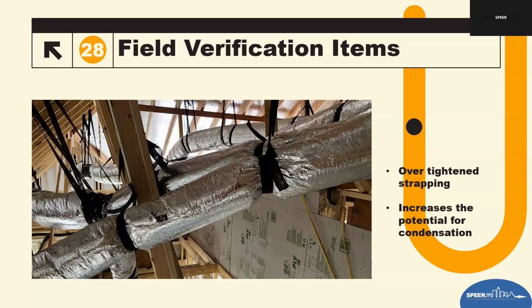So we need to make sure those are not over tightened, because that will build up more heat in the duct. The system will produce 55-degree temperature, and at the supply vent you're only getting 67. That's going to be contributed by this. Things like this, sharp bends, kinks, laying against framing members, touching roofing decks, overstrapping of the insulation, all increase temperature running down the duct. So now we're not worried about how much CFM, we're worried about the fact that we are overheating that air before it gets to the house.